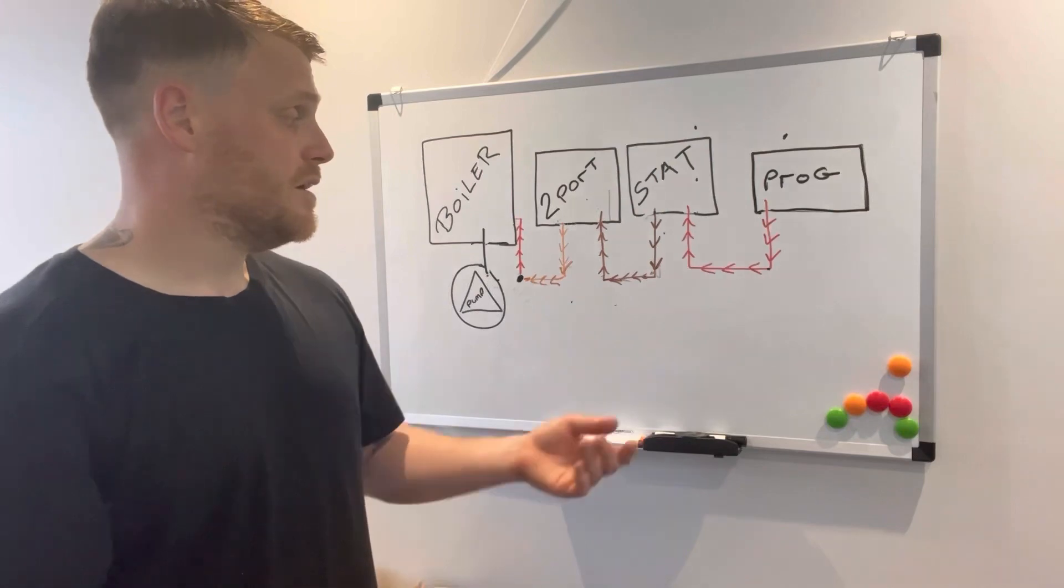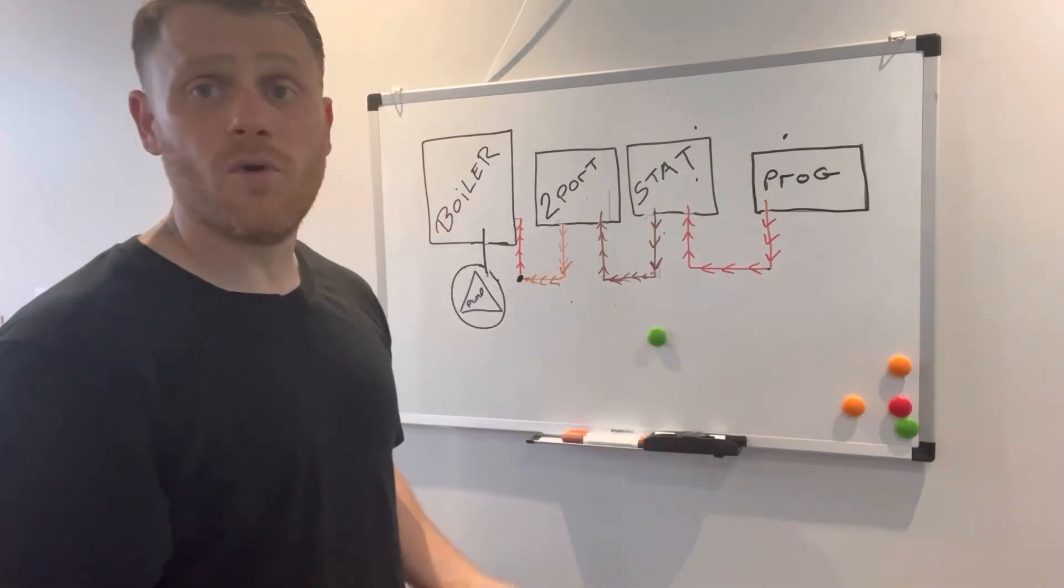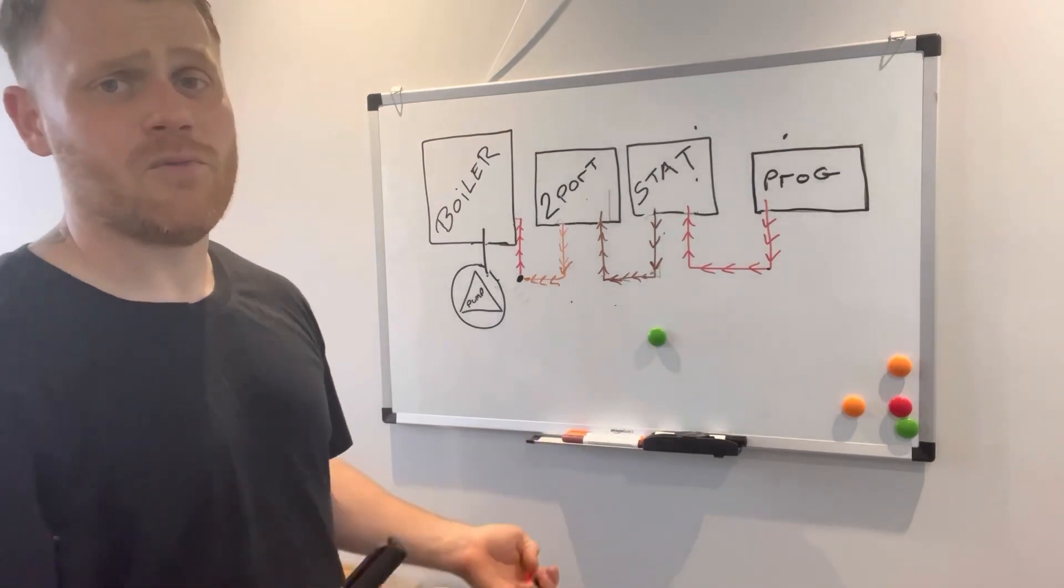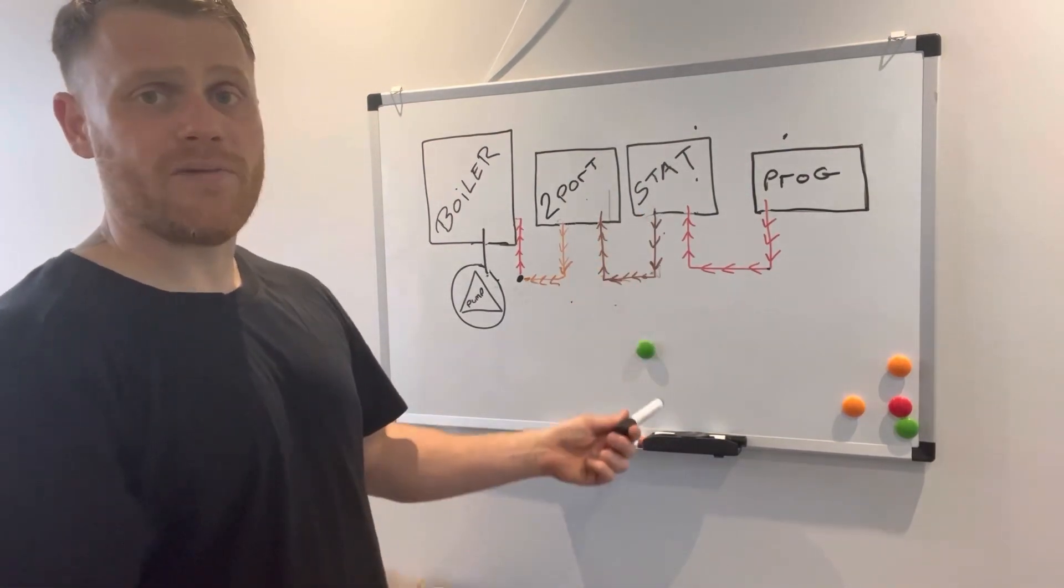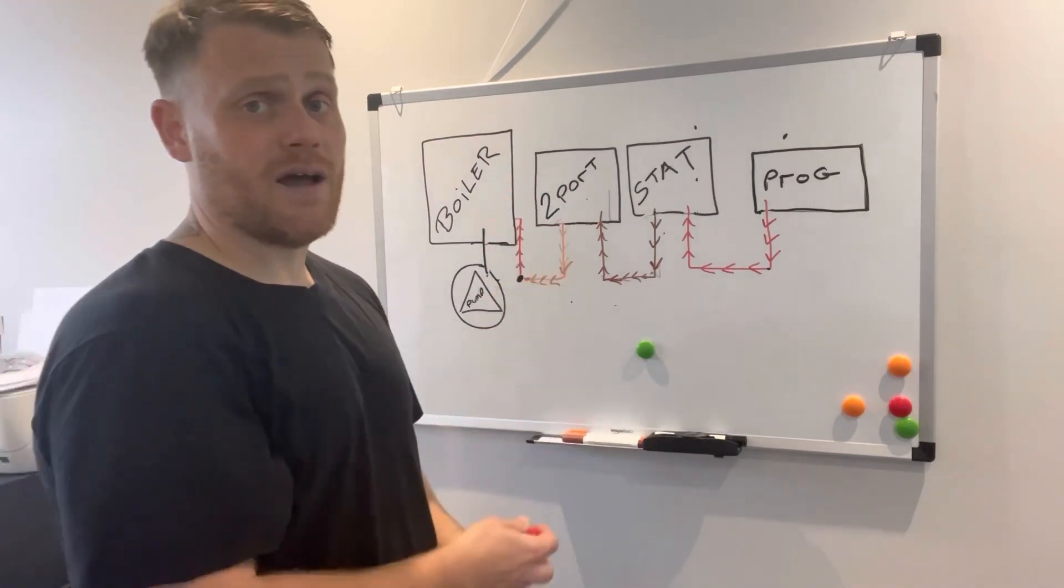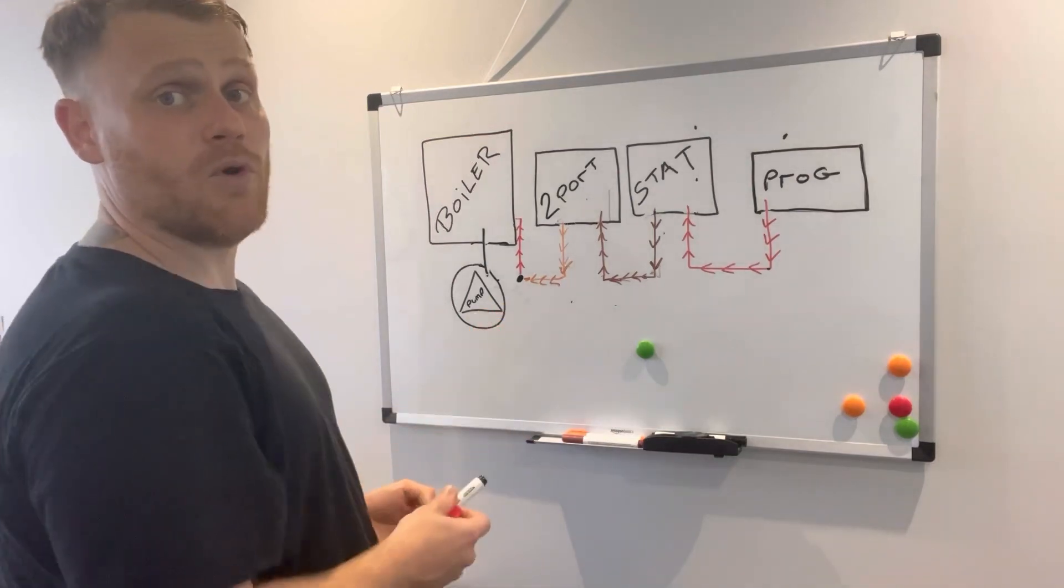It comes in really handy for fault finding as well. So let's just say there's a fault on this one, we've got no hot water, no heating, whichever. What you could do is find an earth point, put one of your probes on there, and we're just going to use our other one to track the wiring. I always go for the brown wire.